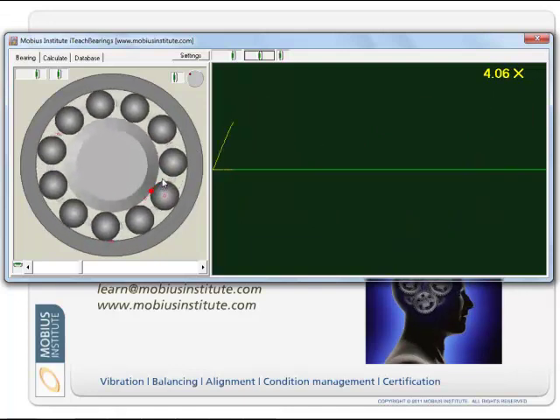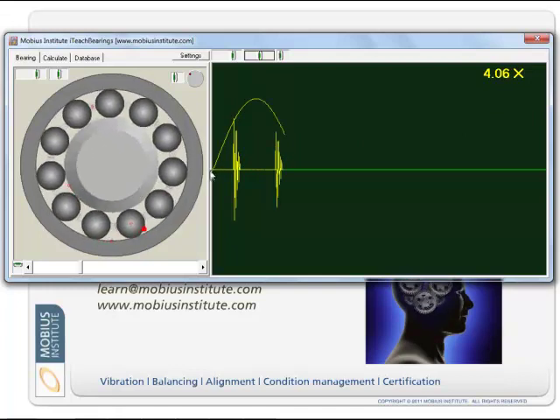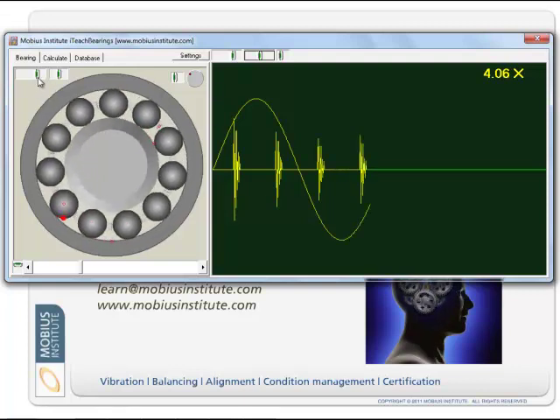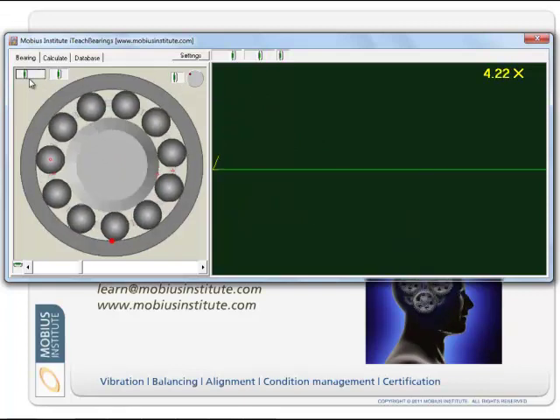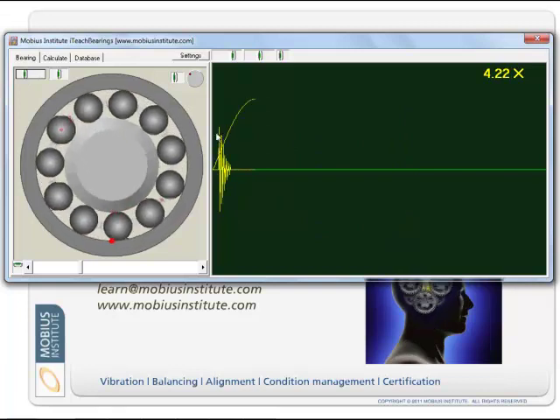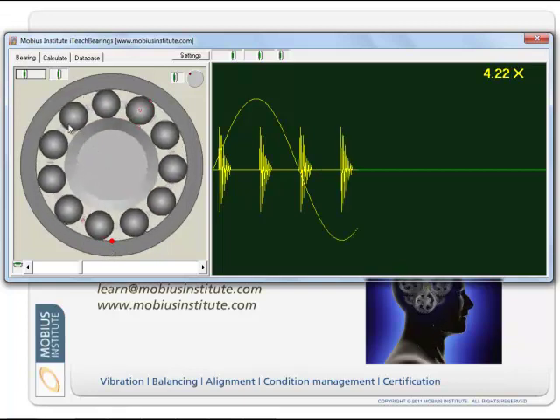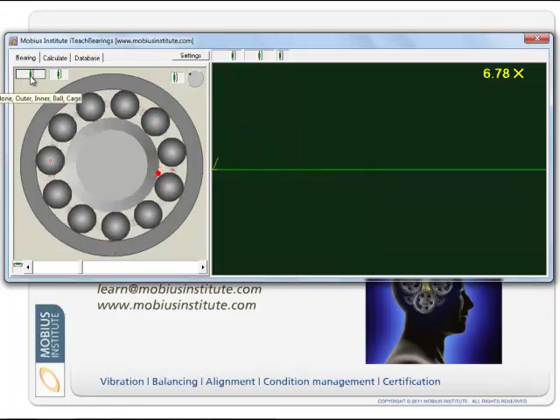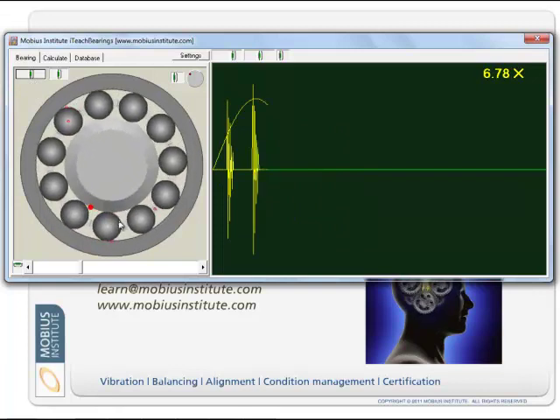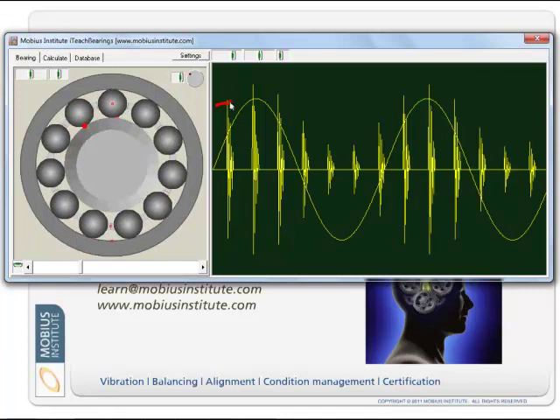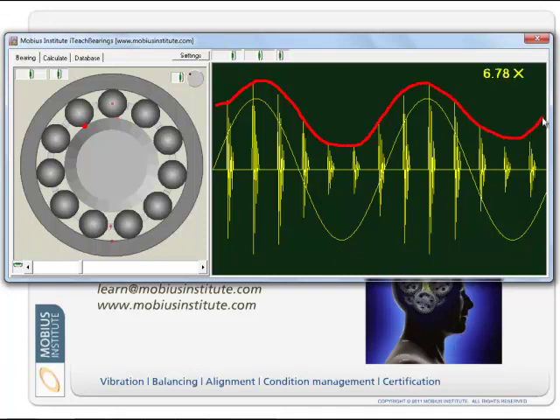There's a certain modulation as that ball rolls around the bearing. As we go into the load zone, those peaks are stronger — the impacts are stronger as we go through the load zone. And out of the load zone, they're weaker. For example, if I choose a fault on the outer race, we'll see that each pulse is the same amplitude because the force of the impact is always the same. Whereas if I look at a fault on the inner race, then as it goes through the load zone the impacts are stronger and then weaker. We can even draw on here and see that modulation effect. You can see in this case the defect frequency is 6.78.